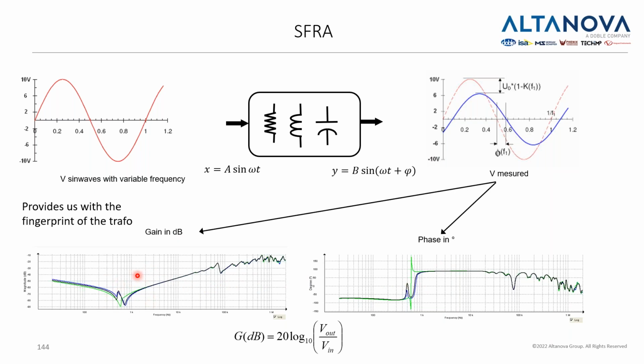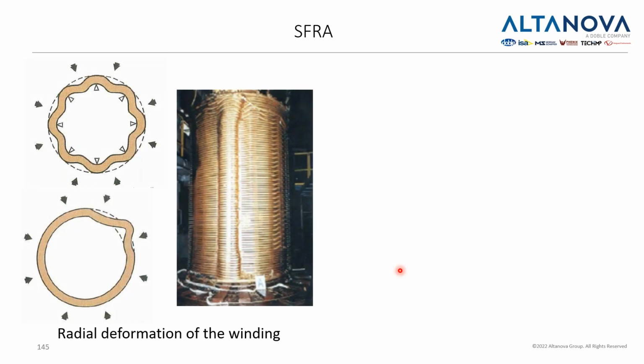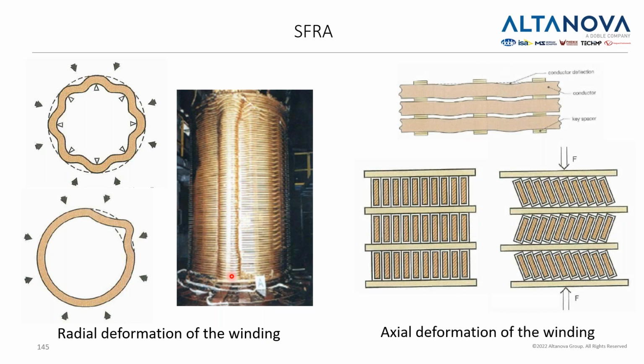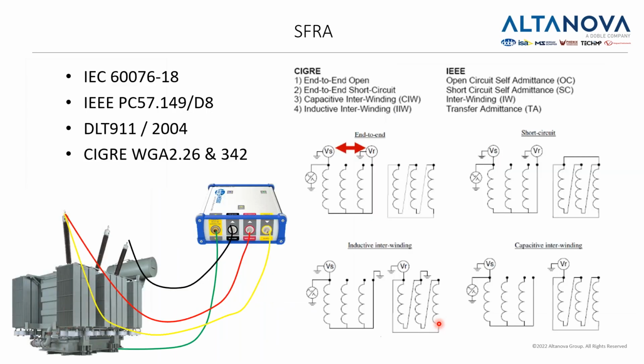So this would be the change in amplitude as the frequency changes, and this would be the change in phase as the frequency changes. And we can detect something like this. So you see this bulge on the winding, it wasn't there when it was produced, but the high current passing through the transformer made it happen. You will not be able to see that when you do some other tests, but SFRA will show this very nicely. And there are different ways. This is a radial deformation, and this is an axial deformation.